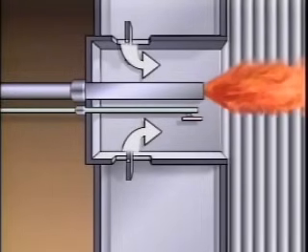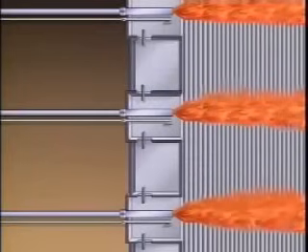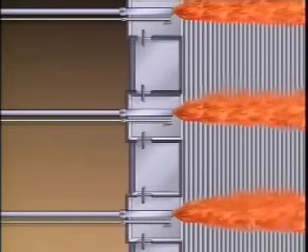The air registers provide a means for regulating the flow of air through the burner and help create turbulence. Once air, fuel, heat, and turbulence have been provided in a controlled manner, the chemical reaction of combustion can take place efficiently. The time element of combustion is satisfied by the design of the furnace as a large open space in which fuel and oxygen have time to mix thoroughly and react completely.